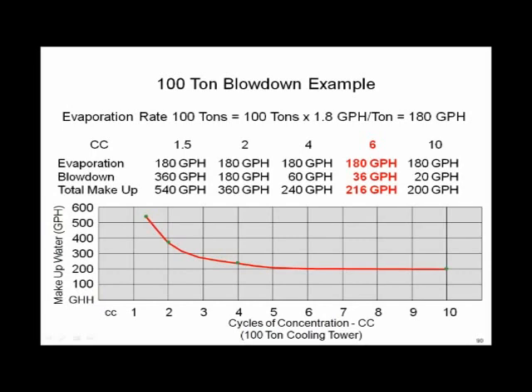Ladies and gentlemen, water usage in this country is becoming more critical. Whether you like it or not, we're going to be dealing with this for a long time to come, and the codes are going to get tighter and tighter and tighter. The old days of just blowing a tower down, not paying any attention to how much water is gone, are over. You're going to have some system to control the cycles to manage and save as much water as possible. Reasonable cycles of concentration in cooling towers are probably 4.